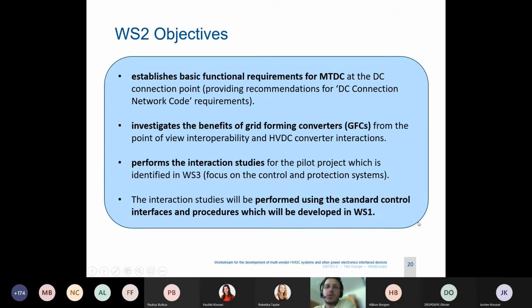Workstream 2 has been developed with objectives to address and establish basic functional requirements for multi-terminal DC grids under a multi-vendor environment. The main focus at the start of this workstream is to develop functional requirements at the DC connection points, but also to go to the AC side and investigate the benefit of grid forming capabilities.